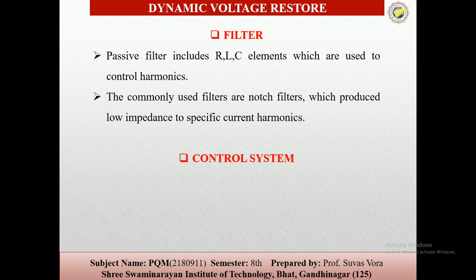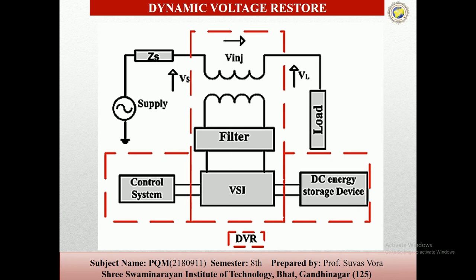And the last one is the control system. The control system is used to control the sampling frequency and switching frequency, and to control the actions of the interactions, finding the three-phase voltage before and three-phase voltage after the DVR system, then the current to the ground DVR and the DC link. So you can see here the actual dynamic voltage restorer, or DVR, system. As we saw, this is the supply system, which is connected to the transformer, here the filter system, here the voltage source inverter system, which is connected to the control system and the DC energy storage device.